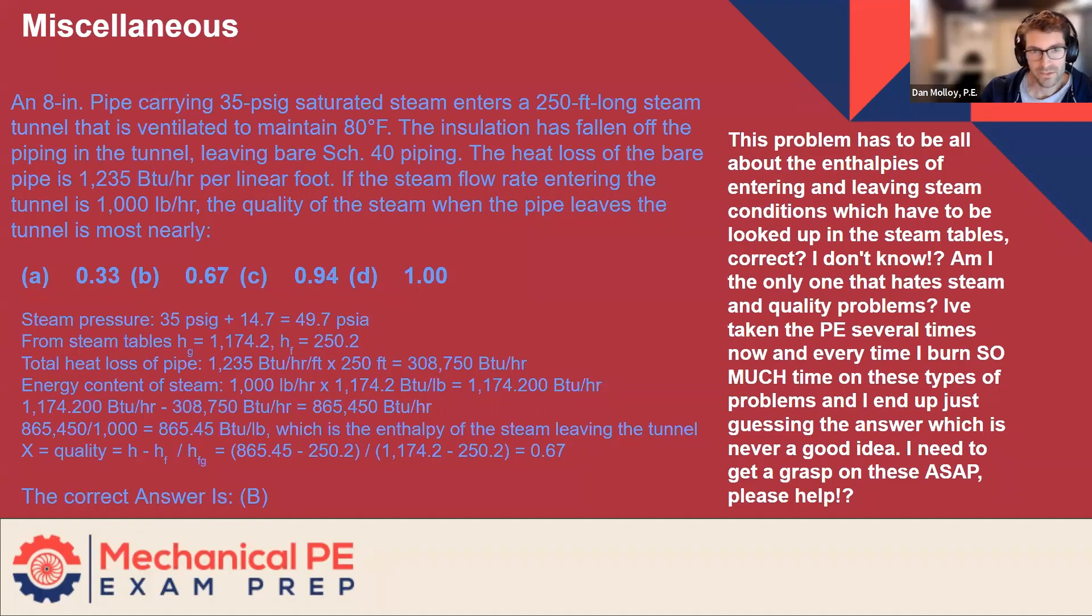Alright, let's just break it down. An 8-inch pipe carrying 35 PSIG saturated steam enters a 250-foot-long steam tunnel that is ventilated to maintain 80 degrees. The insulation has fallen off the piping in the tunnel, leaving bare Schedule 40 piping. The heat loss of the bare pipe is 1,235 BTU per hour per linear foot.